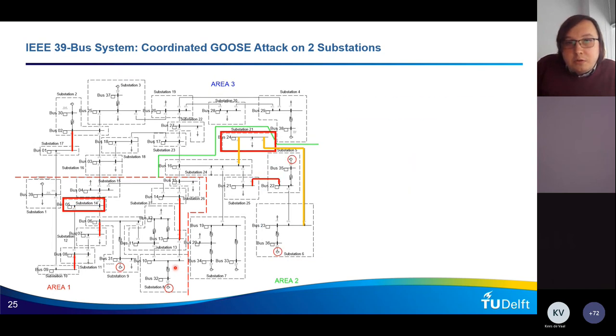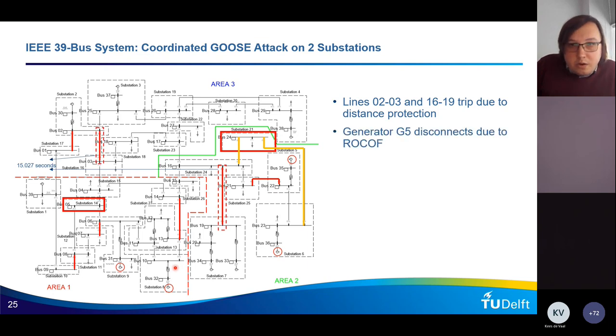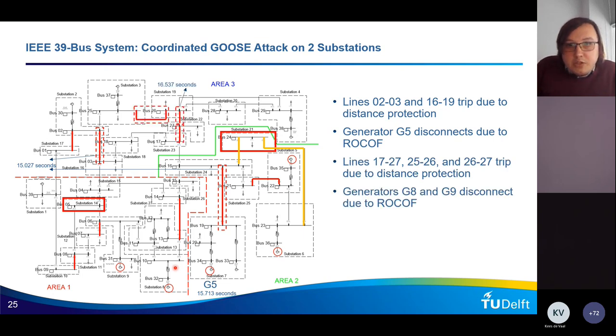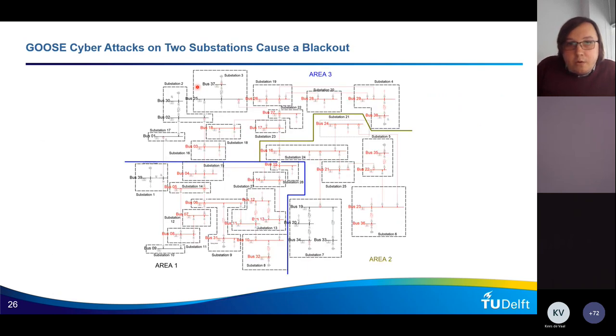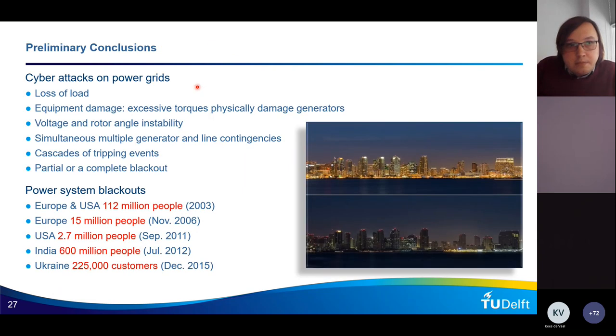So it's kind of similar to the previous scenario. More lines are disconnected on distance protection and more generators are disconnected by their interface protection. And as you see, the cascade continues happening. So we are reaching 16 seconds from when we started the simulation. So it's pretty fast, 18 seconds, the whole power grid collapses. So this small test system collapsed in about 18 seconds.